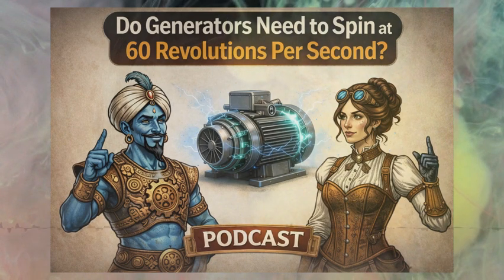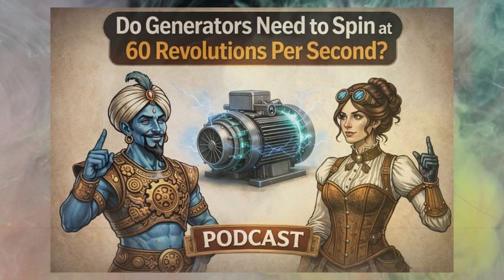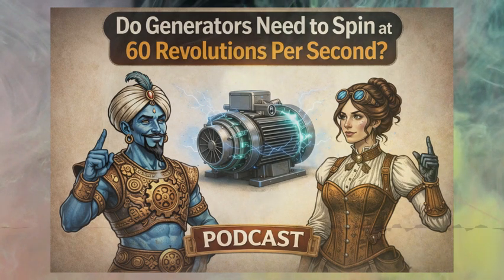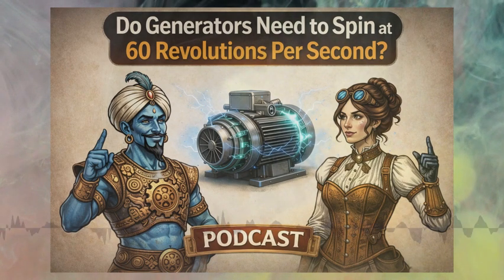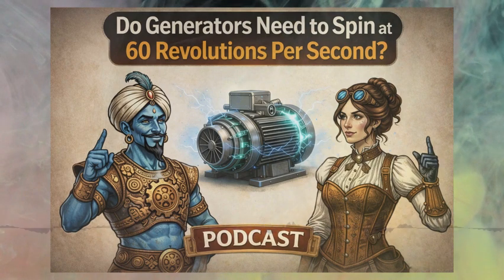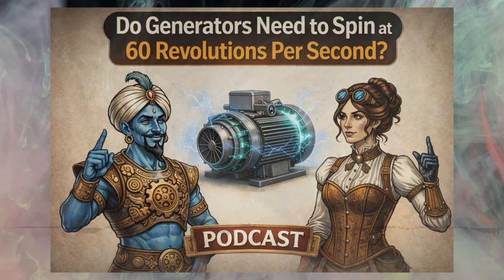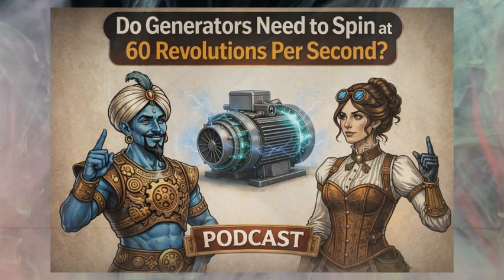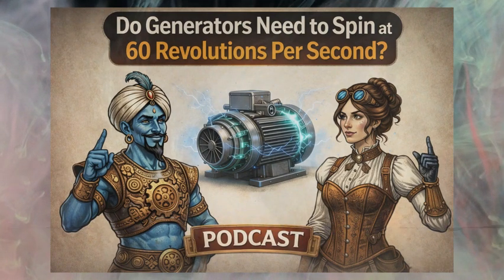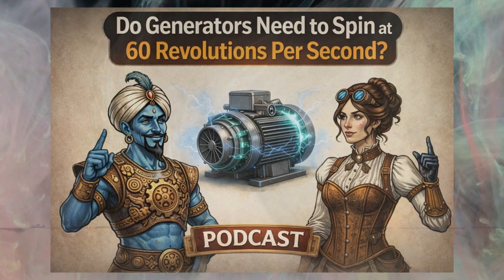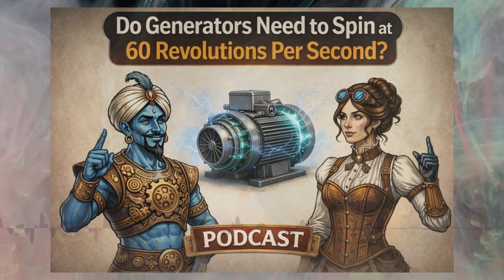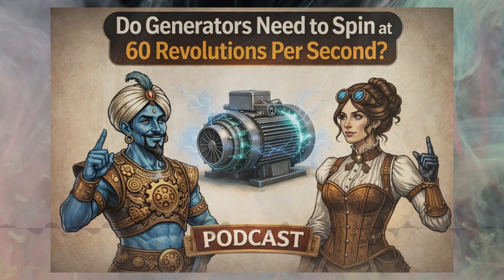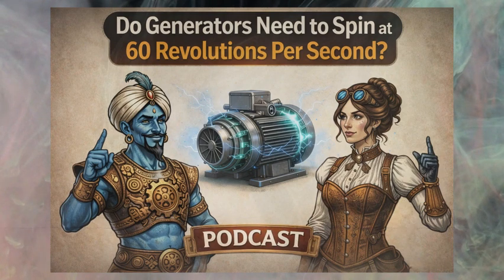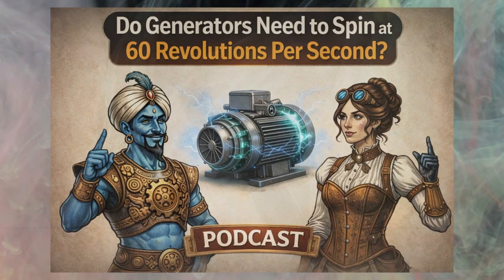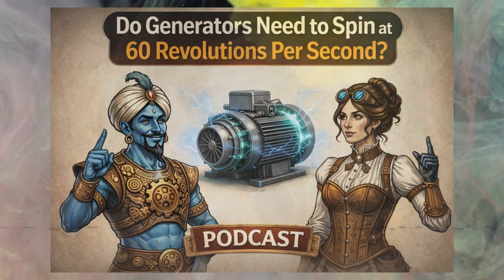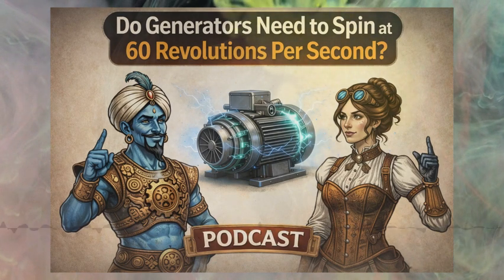It's a story about magnetic geometry, it's about physical limits, and most importantly, it's about something called the magnetic pole. And to get there, we've pulled together a whole range of sources. We're looking at foundational engineering principles from old naval training manuals, some deep technical specs on AC generators, and even historical notes on how we ended up with these utility frequencies in the first place. We're going to explore the anatomy of a generator, the core frequency formula, the physical reasons for high-speed versus low-speed designs, and then the ripple effect all of this has on literally every electric motor plugged into the grid.